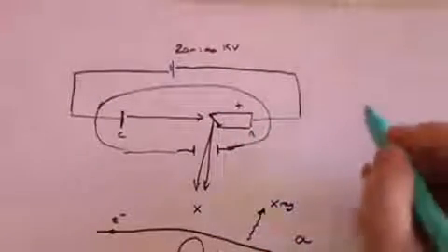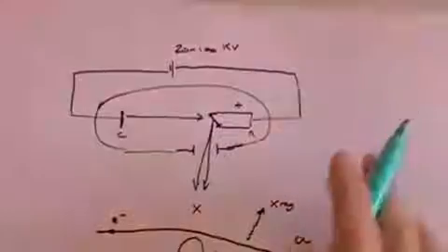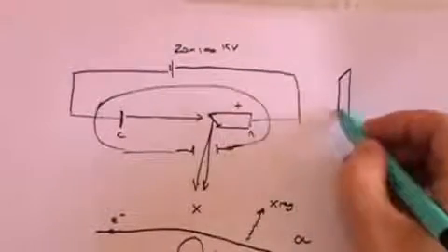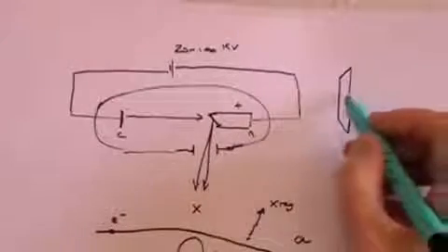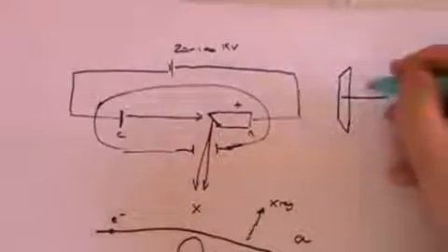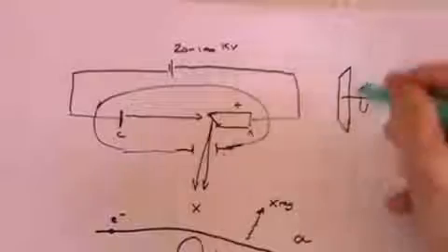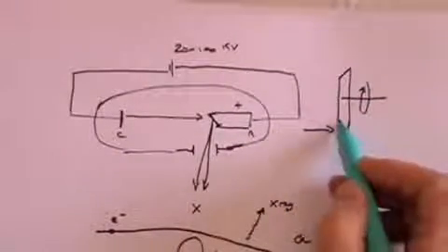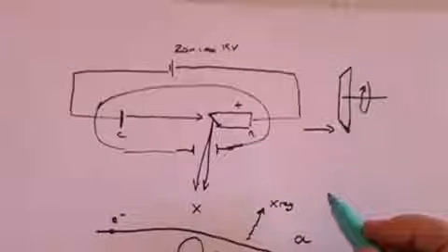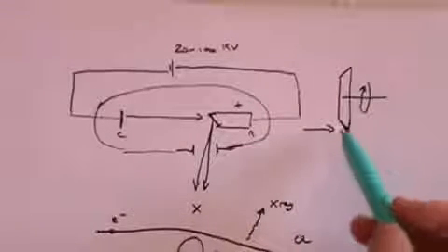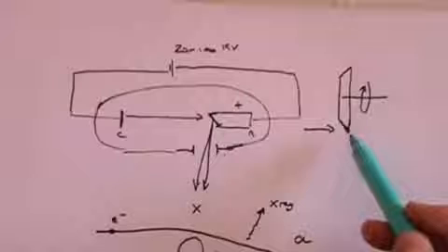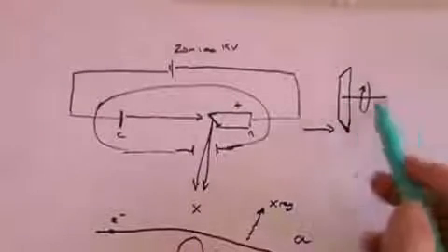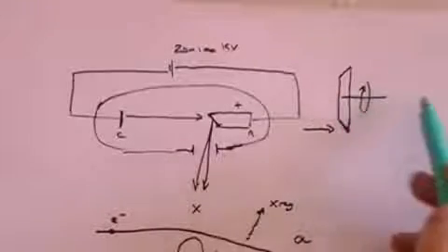So what you tend to find is that the anode is shaped as a circular disc, and it's constantly spinning, kind of on this axis. The electrons are hitting the slanted part of the anode there, but because it's spinning, not one single point is being constantly heated, and quite often there's a means of getting that heat to move away.